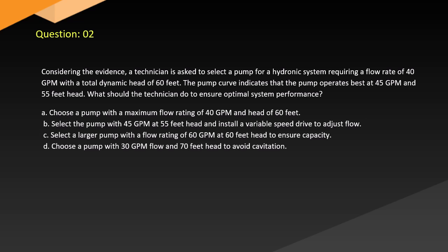A. Choose a pump with a maximum flow rating of 40 GPM and head of 60 feet. B. Select the pump with 45 GPM at 55 feet head and install a variable speed drive to adjust flow. C. Select a larger pump with a flow rating of 60 GPM at 60 feet head to ensure capacity. D. Choose a pump with 30 GPM flow and 70 feet head to avoid cavitation.